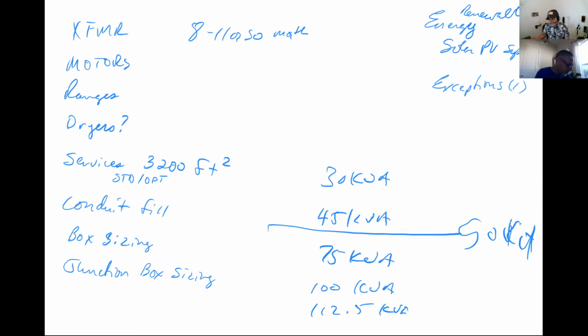The 12 inches is not really a rule that we see very often, but it's probably not a good idea to stick it against the wall because they need ventilation and airflow, otherwise they get hot. What you're talking about would most likely be in 450.21, just FYI. Yeah, I think I just circled it. Now, there are some tables for separation between a metal sidewall of a cabinet or distribution panel and energized equipment, but that's in a different section. It could apply to transformers, but also to MDPs or switchgear or anything with exposed electrical parts within a metal cabinet.